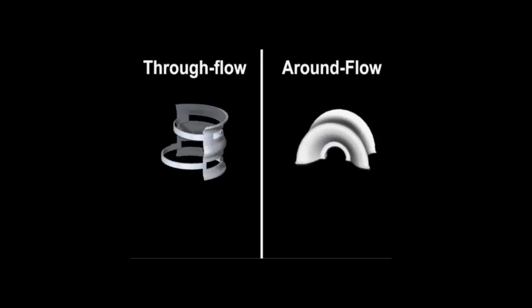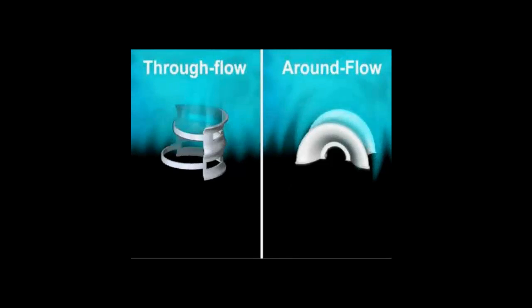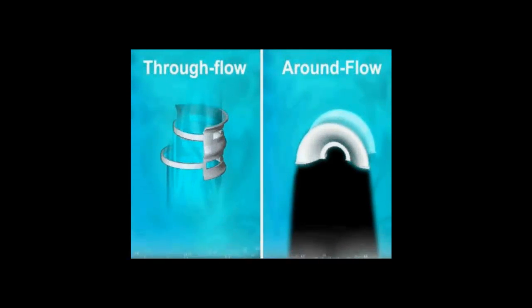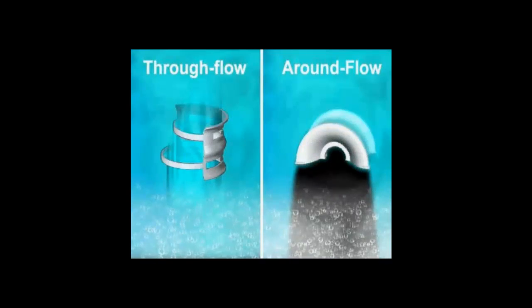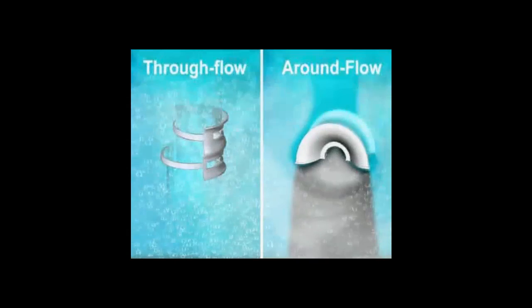The distinction turns out to be quite significant and is related to the ratio of form drag to skin friction incurred by flow of vapor and liquid through the packing. All modern random packing is of the flow-through type with reduced form drag.